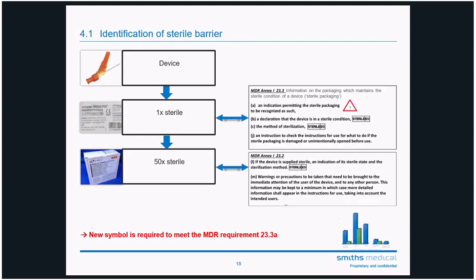Absolutely. That's a very good question, and I'm trying to find the relevant section here for you. Bear with me one second. So it's in the general principles that we have had a look at. Basically, information required on the label shall be provided on the device itself. If this is not practicable or appropriate, some or all of the information may appear on the packaging for each unit and or the packaging of multiple devices. So the MDR does still offer the option to move that information.